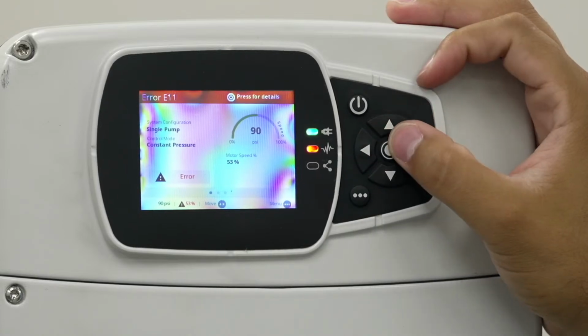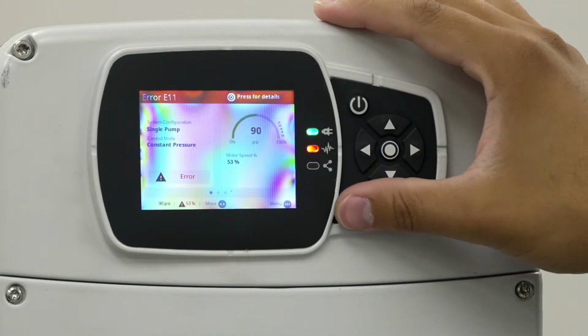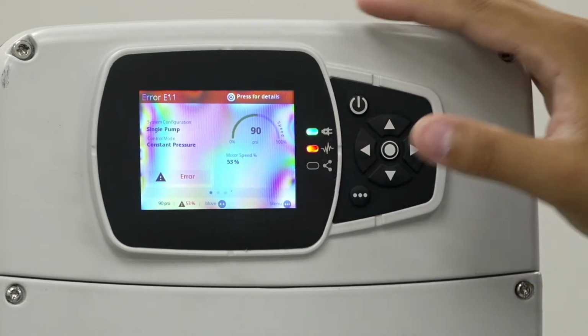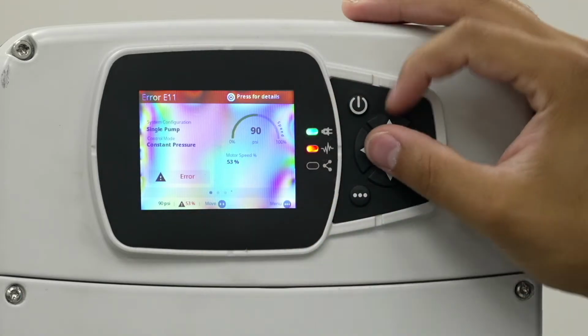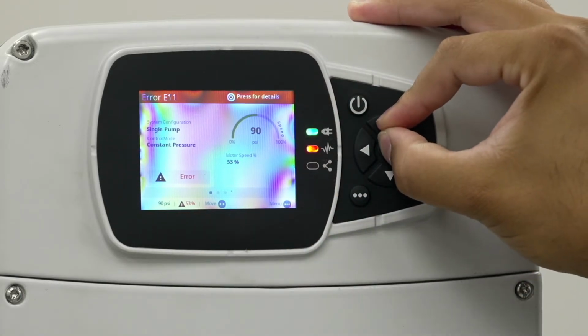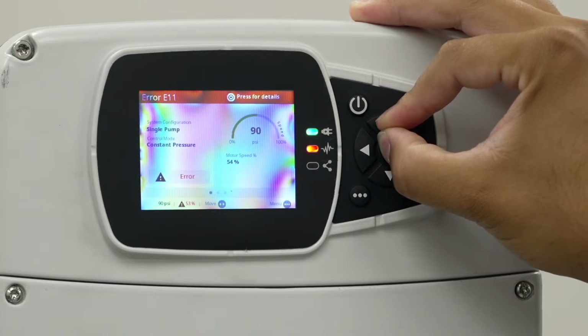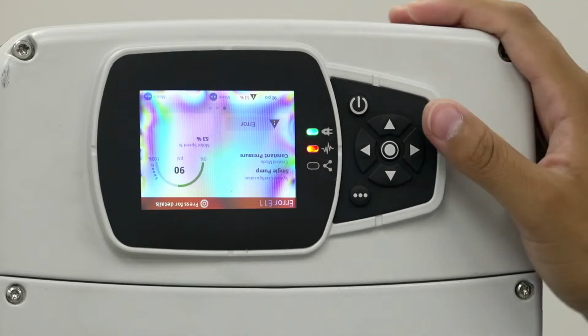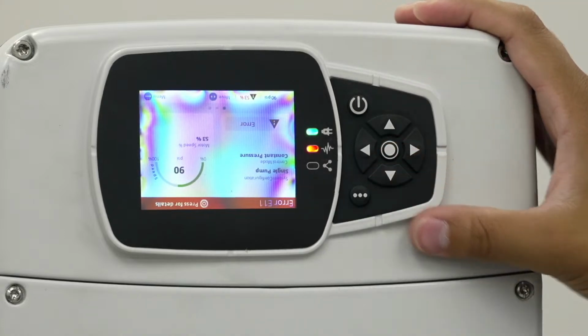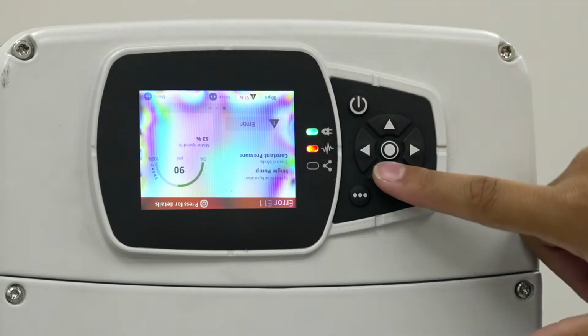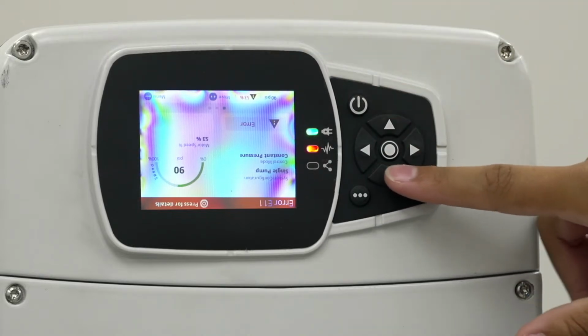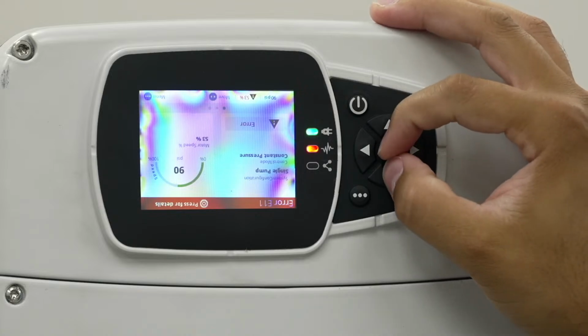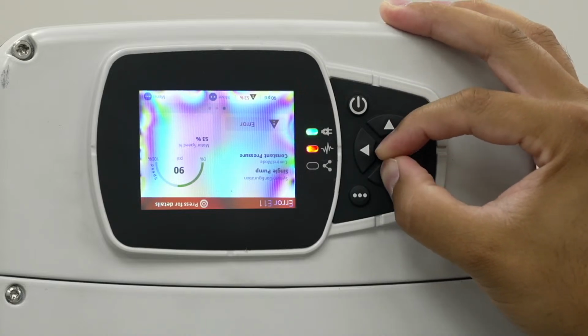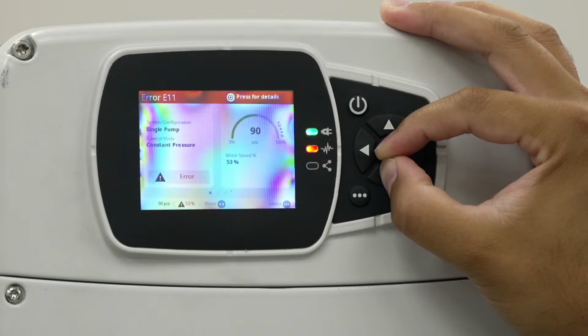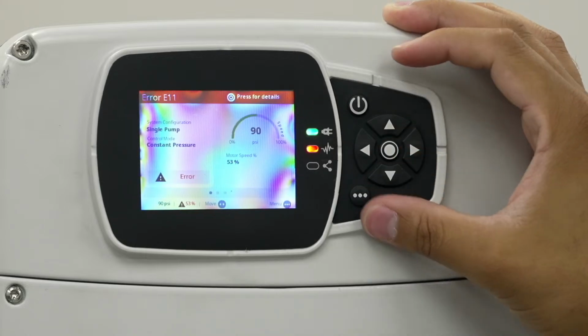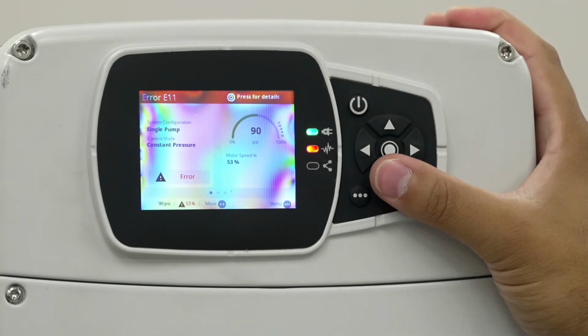Some shortcuts. Right now we have the unit standing up, but it could be on a horizontally mounted pump, so you could be standing on this side of the pump or this side. We have the ability to long press the enter button and up button simultaneously. By doing that, it flips the screen 180 degrees, depending on what side of the unit you're on. Now the screen's the opposite way. This would technically be my up button, right? It's associated with the screen. So if I wanted it back, I'd hold the enter button and technically the up button simultaneously still, and it flips back.